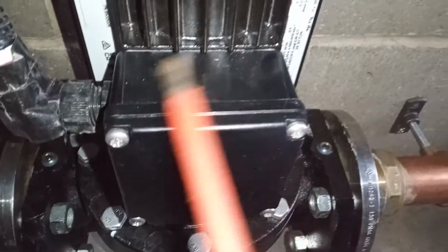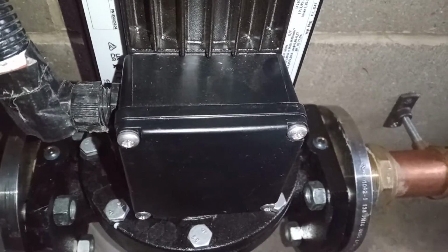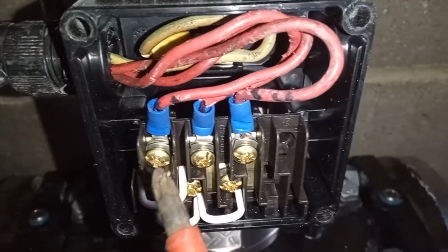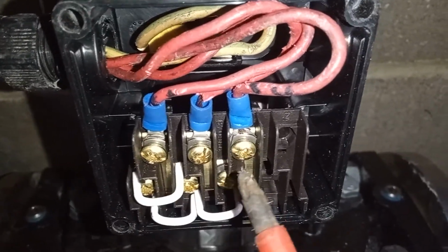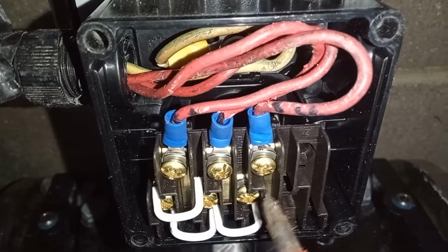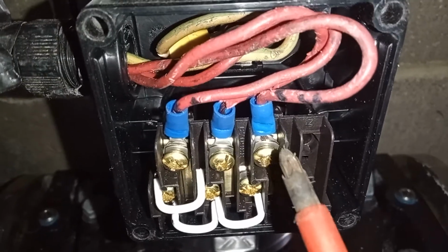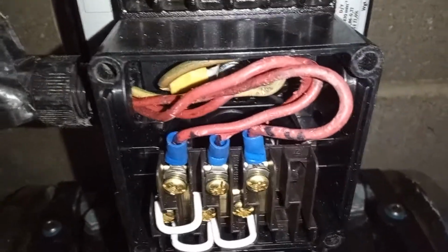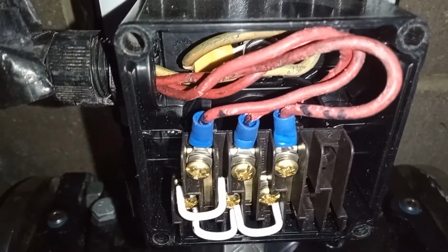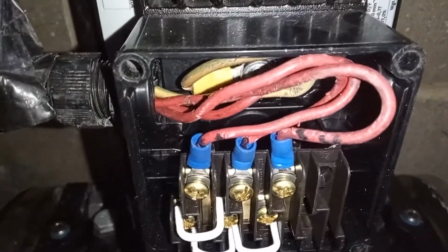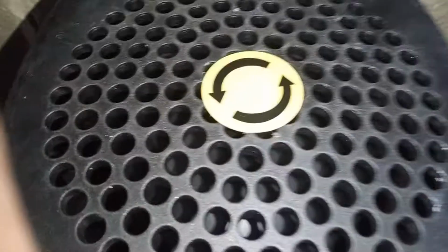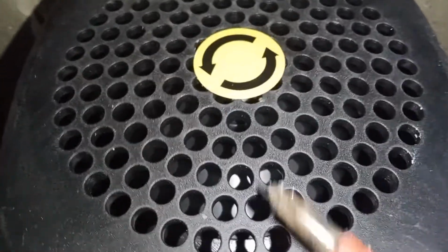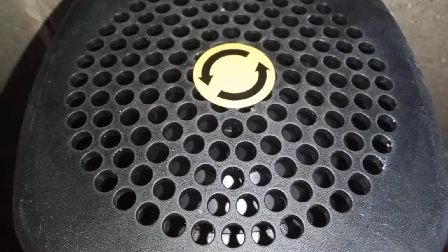So what happened is we have the phases inside here. You have a phase here, a phase here, a phase here and a phase here. They were the wrong way around, so what I did is I swapped live 1 with live 3, and then we have our pump circulating the correct way. So always double check that your pumps are circulating the correct way. All you have to do is turn the power off and turn it back on, and as you do that you'll start seeing that the pump is going the right way or the wrong way.